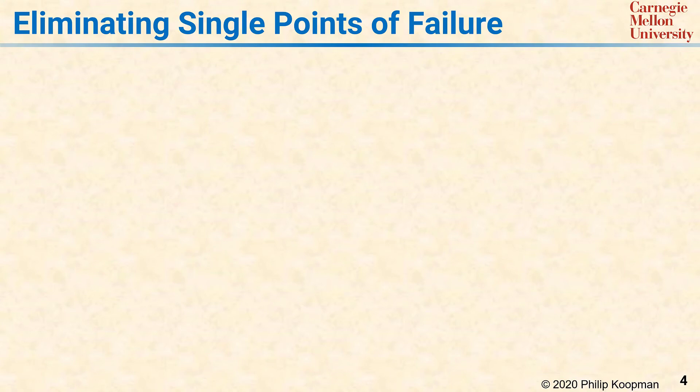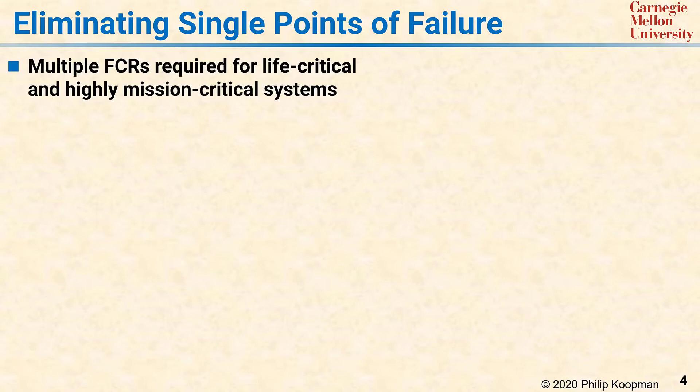Eliminating single points of failure requires the use of redundancy. If your system must be more reliable than the reliability limit imposed by individual component failure rates, then redundancy is the only way to meet your system reliability goals. Typically, redundancy must be used if you wish to do better than about one critical system failure every 100,000 hours, depending on your system design.